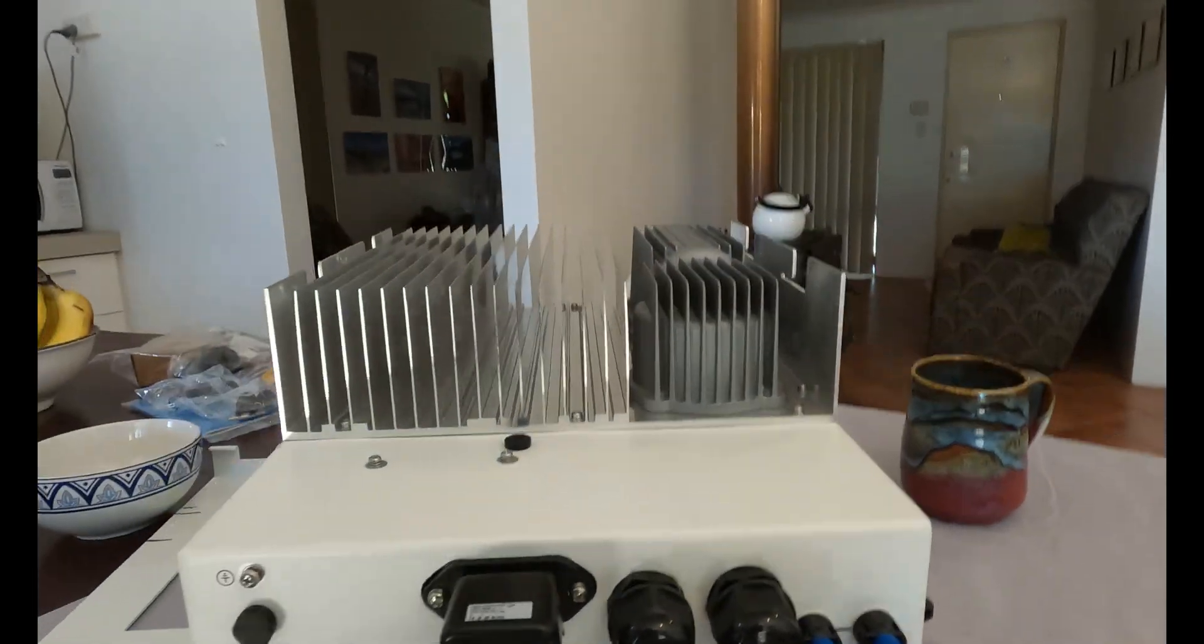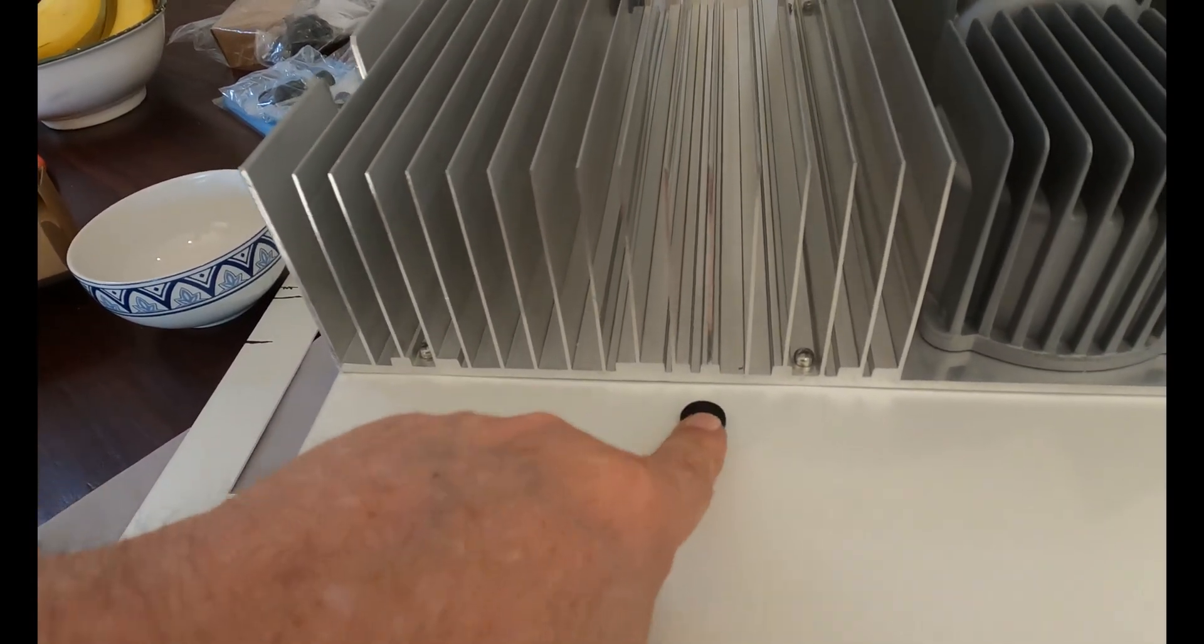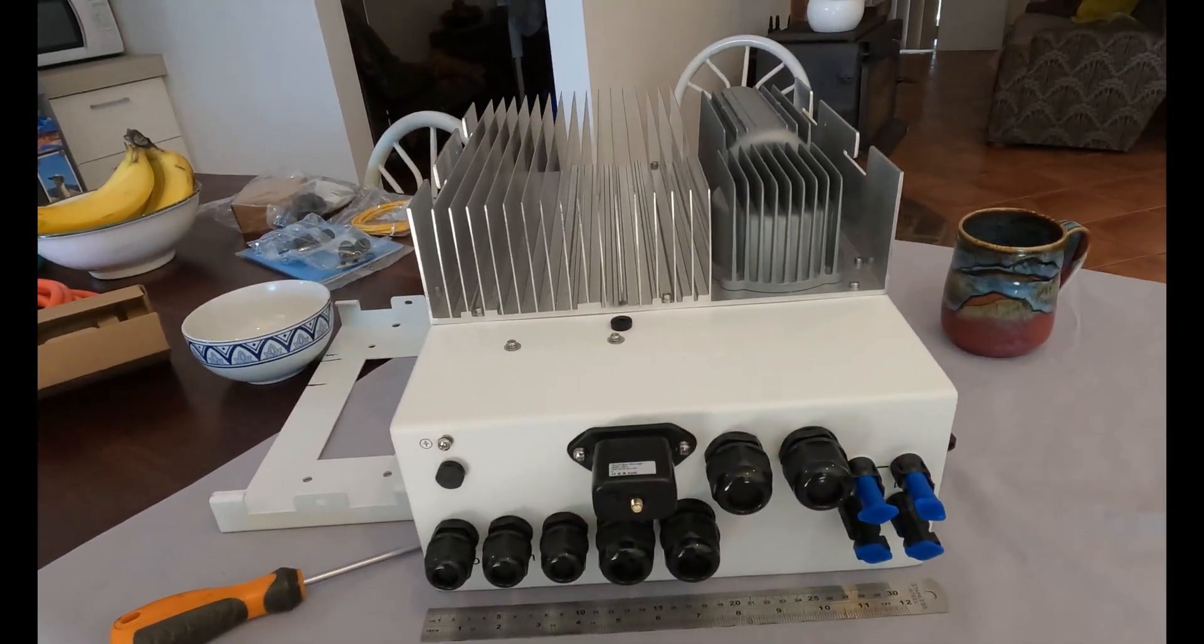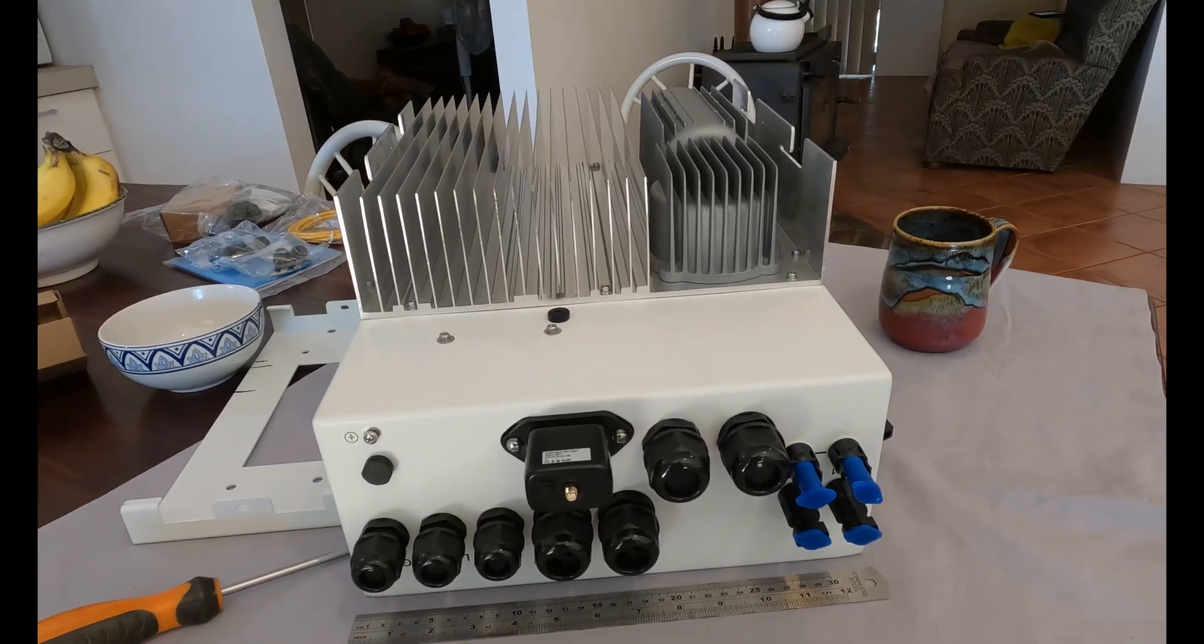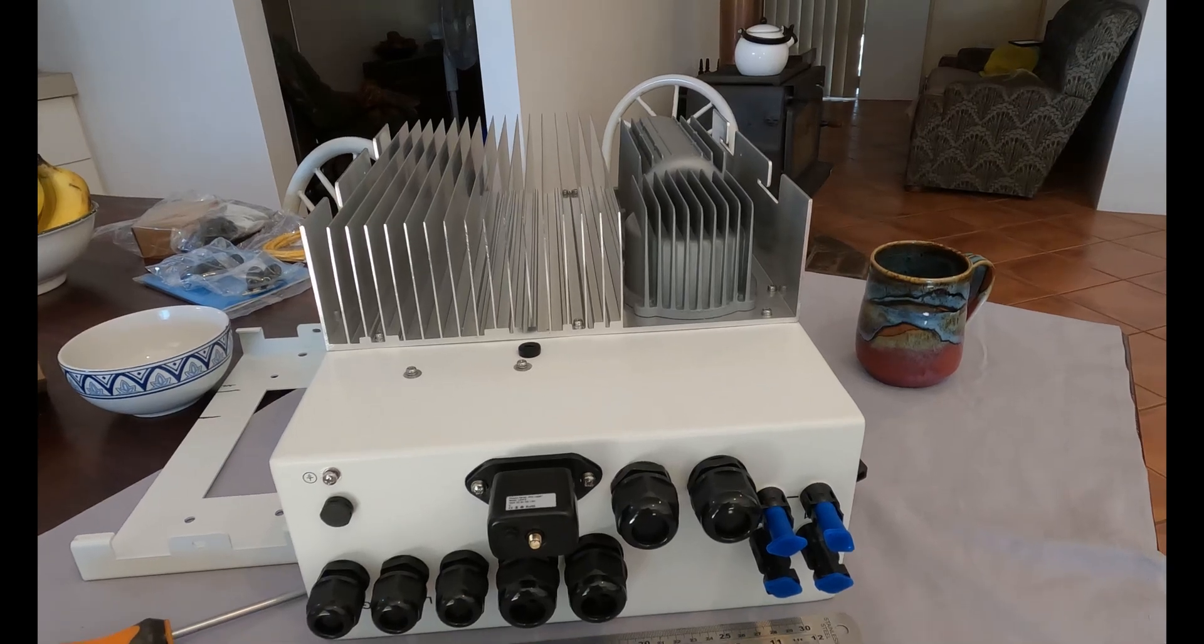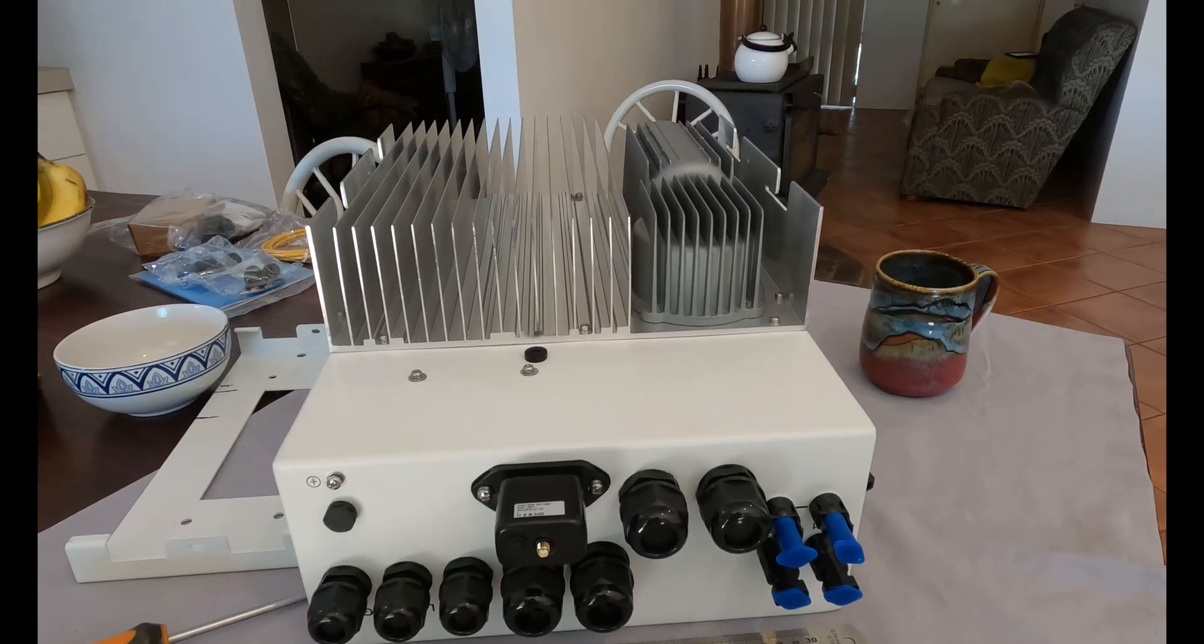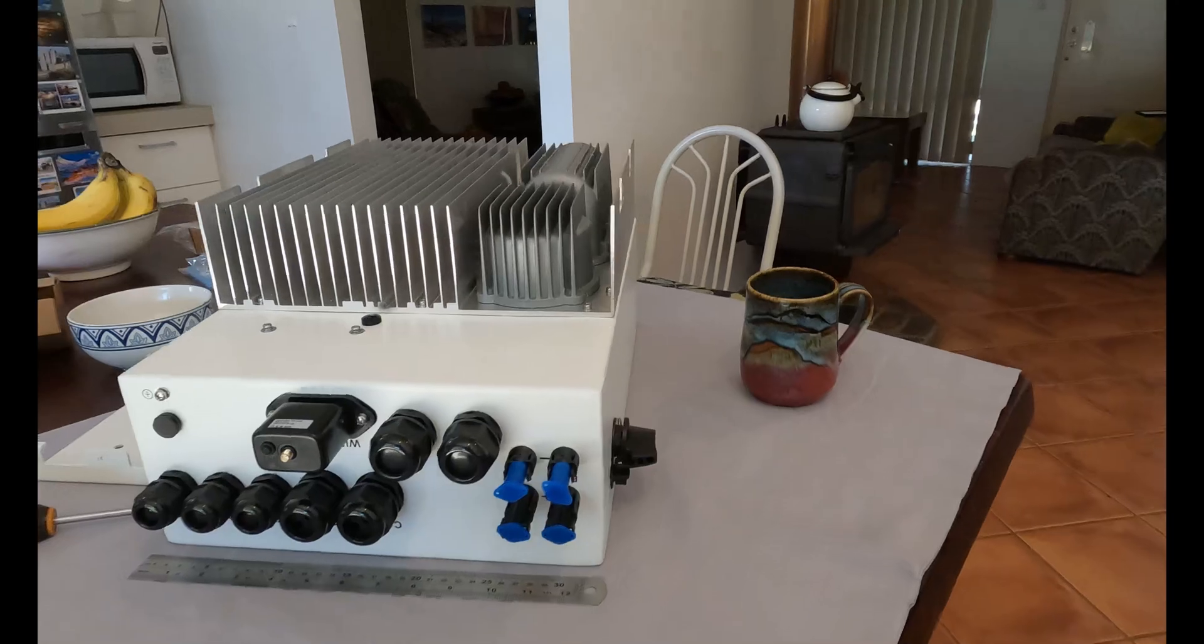Okay, now this is a fanless unit. That's where the fan used to be. That's the outlet for the fan. They make these totally fanless. Now, because it's being mounted into my power cabinet, because it's a closed cabinet, I do have exhaust fans and inlet vents. Do not put this in a cabinet without exhaust fans or inlet vents.